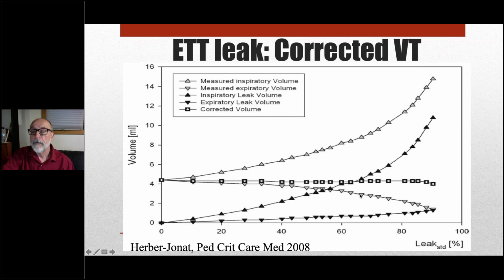And this is the reason why volume-targeted ventilation uses exhaled tidal volume to regulate the pressure delivery. But this was also the basis of being able to calculate what the real tidal volume was. So tidal volume compensation is a real thing in the Dräger devices, and leak compensation has really made a huge difference because before that became available, it was a challenge to ventilate babies who had a large leak around the endotracheal tube, and you really couldn't do it safely when the leak was more than 40%. Now, things are very different.